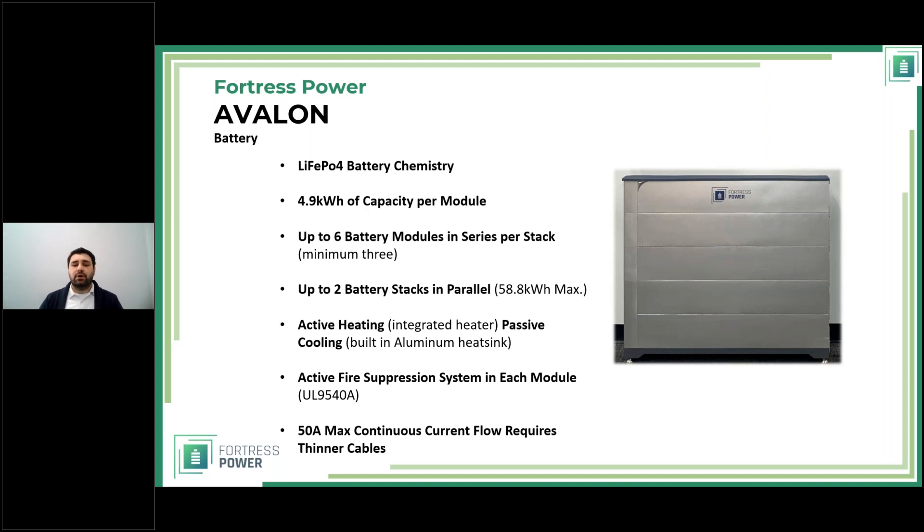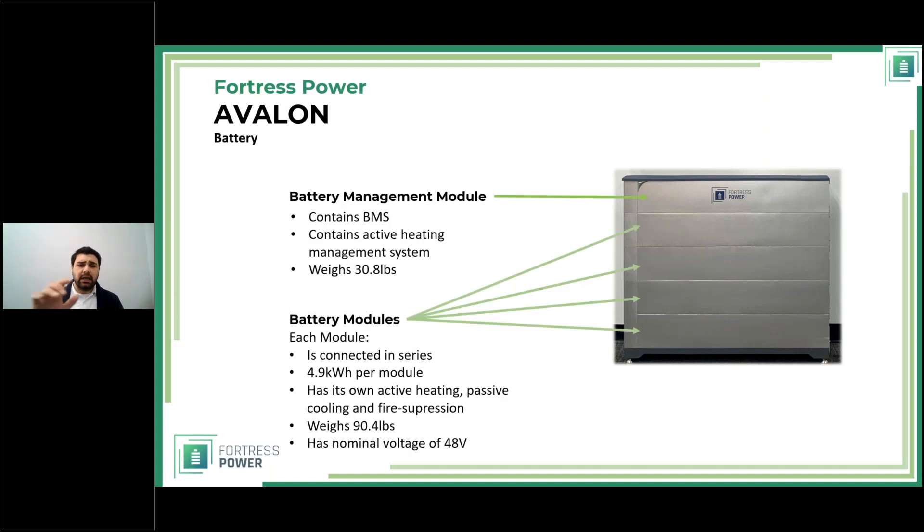These modules are connected in series, so the maximum current flowing to or from the battery is 50 amps. Looking at the modular design: the top module is always the Battery Management Module, which contains the BMS (Battery Management System), active heating control mechanisms, and a built-in charge controller that steps the voltage down — based on the number of modules — to 24 volts to power the battery heaters.